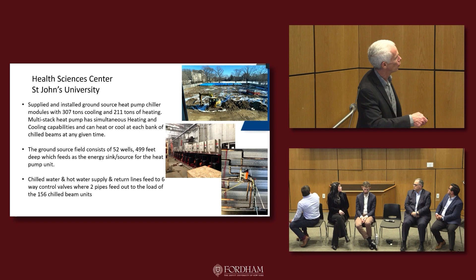There are primary areas supplied by 2 air handling units up in the penthouse that then feed down to the chilled beams. The chilled beams are basically a coil that sits in the ceiling space, and the air from the air handling units goes into the unit, and it induces air across the coil. You provide the heating and cooling effect through the water that's in the coil. It's either heating or cooling in terms of the water that's in there. Again, it has that 6-way control valve, which is fairly complicated. But it basically allows you to provide very efficient heating and cooling to where you need it.